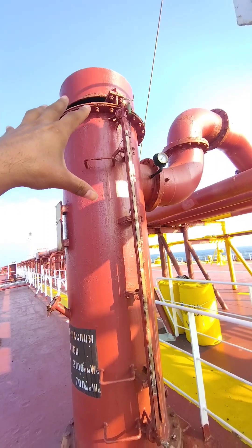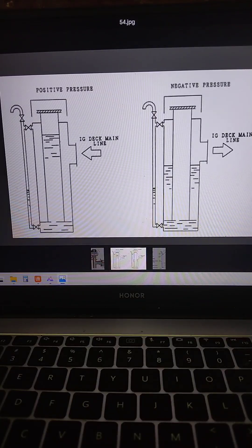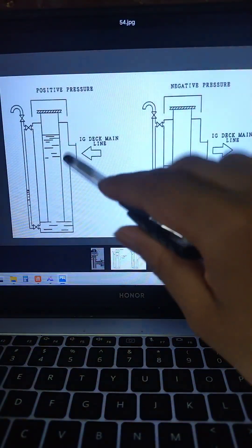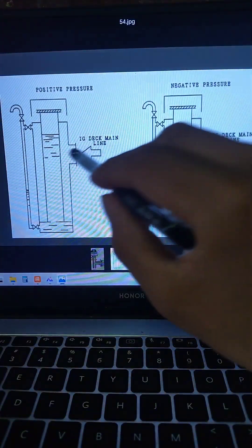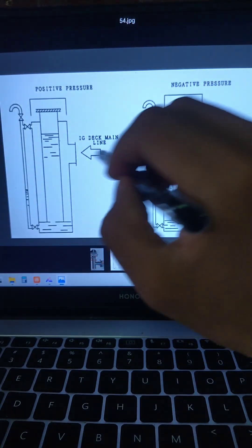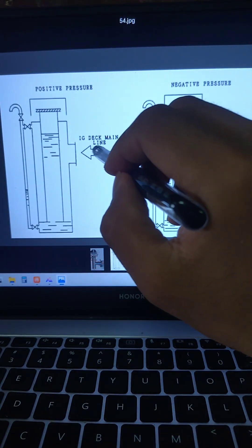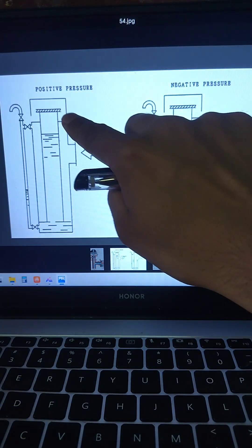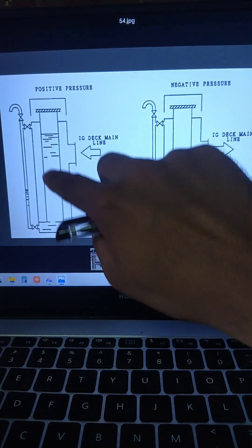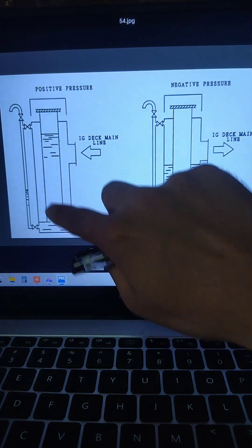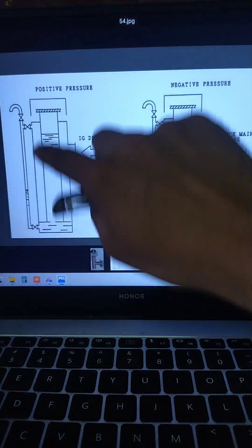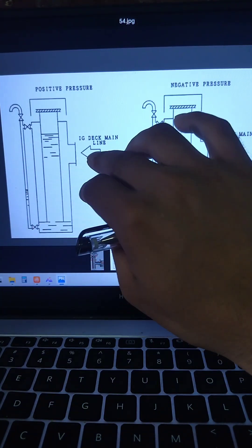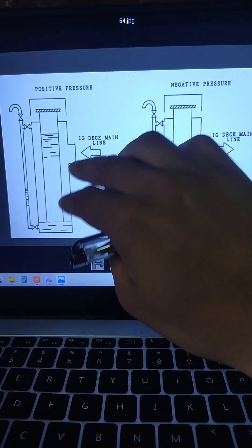For better understanding from this diagram: on the positive pressure side, this is connected with the IG main line and there is liquid inside. When the pressure of the IG main line increases, it pushes the water out from this opening. There is a flame arrester here, and the water will come out — this is the vomiting of water. After vomiting of water, the air will go out and the positive pressure will decrease on the main IG line.